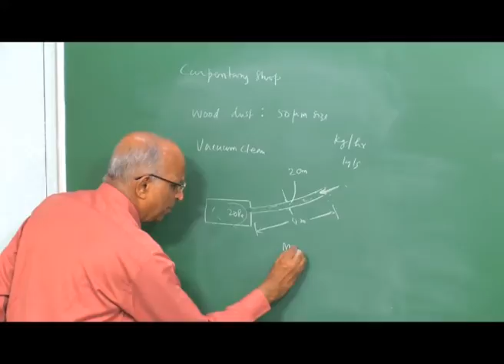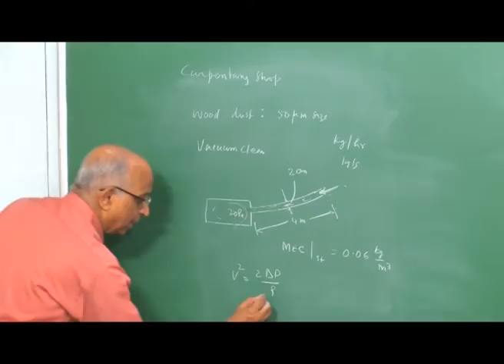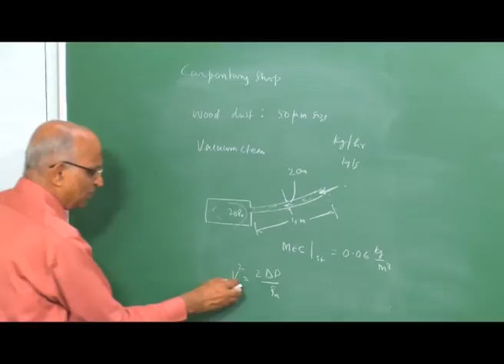Therefore, we say it's sucked with a pressure of 20 Pa with respect to the atmosphere, and therefore the velocity of airflow in this particular passage is going to be v squared is equal to twice the delta p divided by the density of air in the medium. That is the velocity. How did we get this?